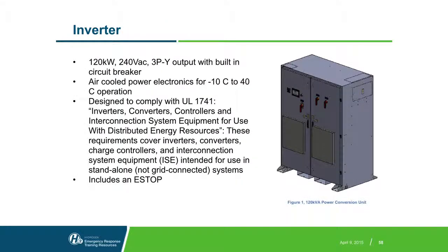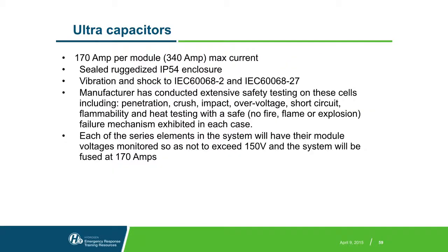An inverter, and there is a user manual that I can make available if there's interest to first responders. Ultracapacitors: the lines running between the ultracapacitor and the other high voltage components, the residual charge will be dissipated on shutdown or if the e-stops are hit, but the ultracapacitors will maintain charge and ultimately dissipate it over a matter of hours. But immediately after it's shut down, they still, of course, can have charge.